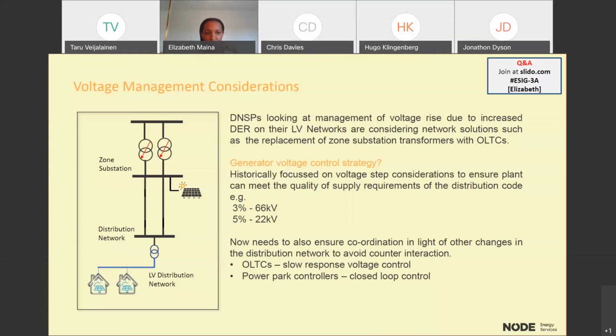You may now see OLTCs introduced at the zone substation, for example controlling the bus voltage at the medium voltage level, as shown in the diagram. So for a project connecting at that same point, whatever voltage control strategy historically just ensured voltage step compliance now needs to integrate well with what's happening at the higher level. When a DNSP replaces that transformer, they introduce another voltage device controlling the same bus a project is trying to connect to.